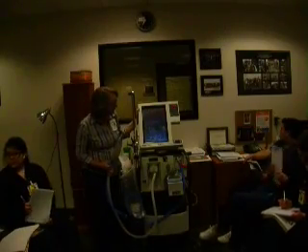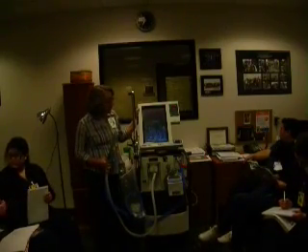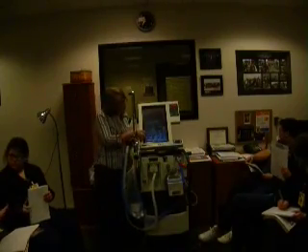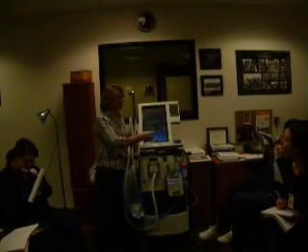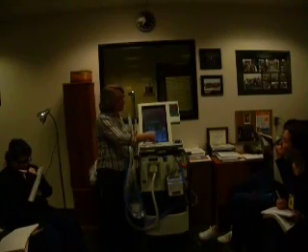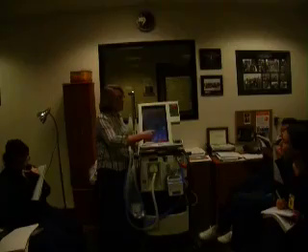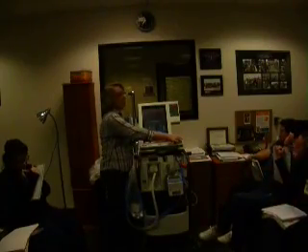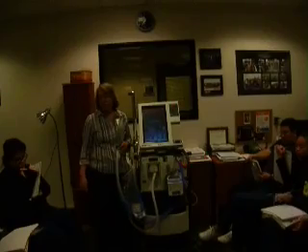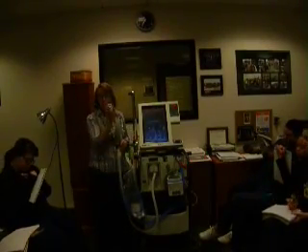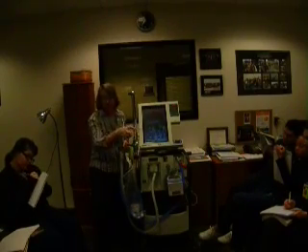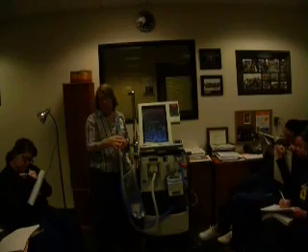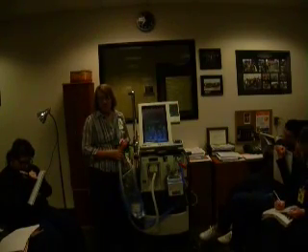Yeah, that'll help. Okay, so then we have minute ventilation. The other thing, you guys, to the left you'll see numbers. The number to the left tells you what your patient is averaging, so you can use that as a guide to where you need to set your parameters, which is on the right. Everything on the Puritan Bennett: you touch it, it turns orange, you turn the dial, and then you hit accept to confirm it. If you don't hit accept, it's like not doing anything at all. So touch the button, it turns orange, turn the dial to make your change, hit accept to confirm it. If you don't hit accept, it goes back to where it was and your change was never made.